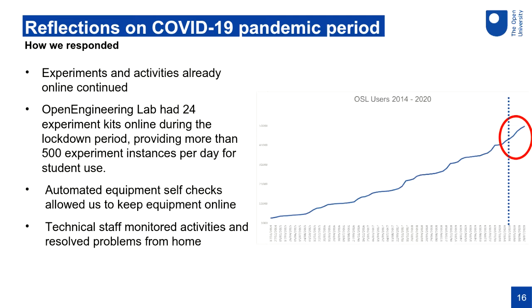Something we really benefited from was the original design of the labs. The designers wanted equipment online 24 hours a day and knew they couldn't provide technician support out of hours, so they built in automatic equipment self-checks run after every student use — typically once an hour — and a more substantial reset in the middle of the night every night. These were designed to run over weekends or maybe nine days at Christmas, but they ran successfully for potentially 60 to 90 days with no one able to go on campus. The system emailed staff if something was wrong and automatically reallocated kit from the pool if a particular piece went down.